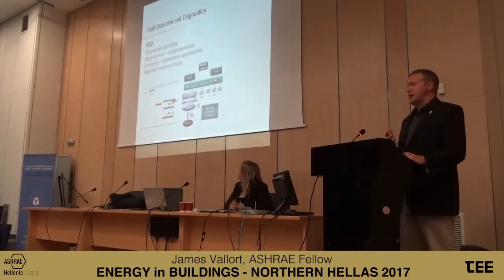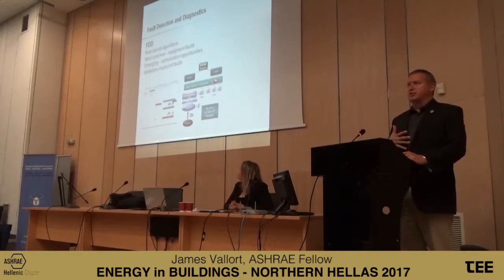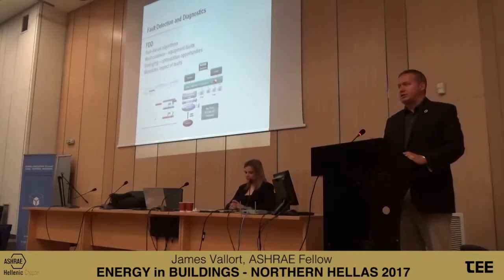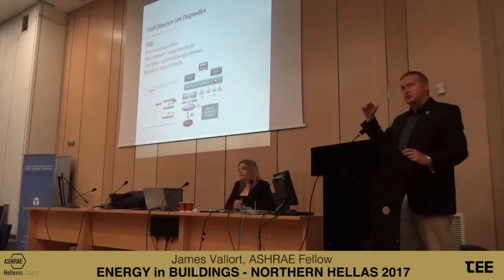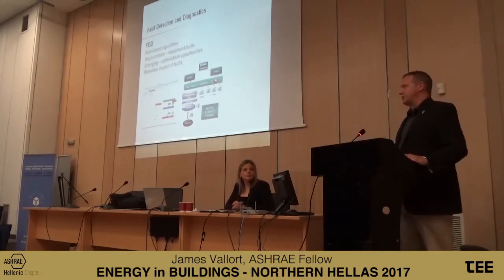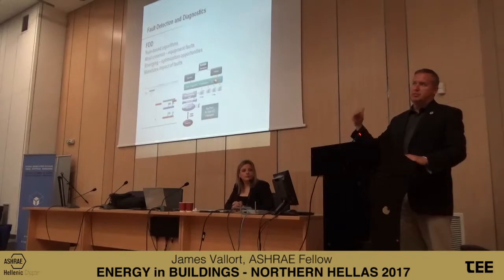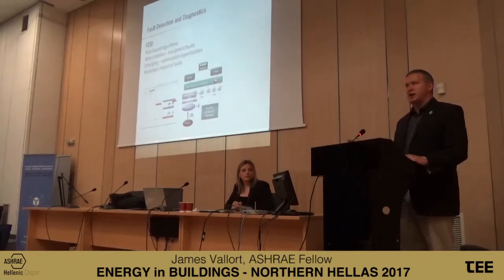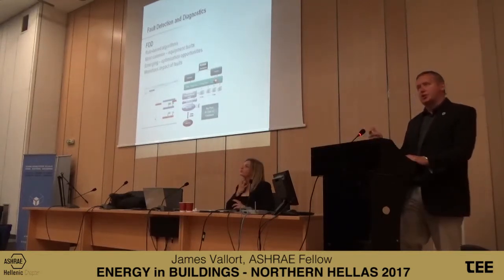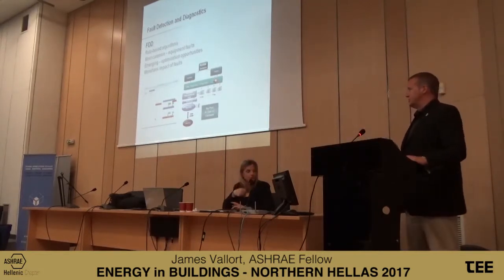Put these logical checks into your building and you can see where there's a fault. One thing you'll often find is if a valve is overridden - you get a phone call, someone says we've got a room full of people, just chill this room down, open that valve 100%, so they lock it, maybe lock the fan speed too. Then the next person comes on shift, goes to another screen on the graphic, and it gets left behind. The fault detection will find that override and bring it back to where it needs to be.